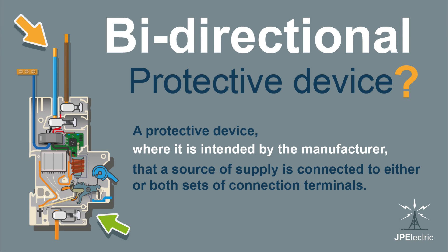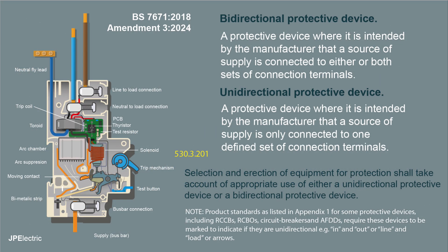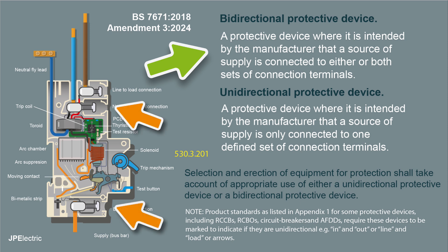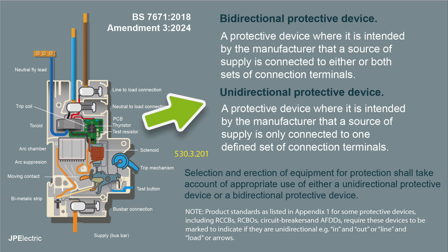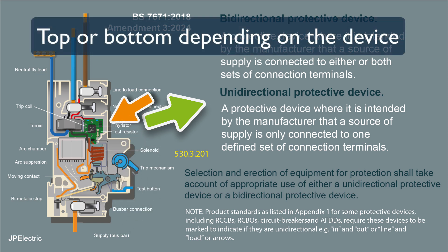Let's have a look at bi-directional protective devices and what they are. A bi-directional protective device is a device where it is intended by the manufacturer that the source of supply is connected to either or both sets of connection terminals. A unidirectional device is a protective device where it is intended by the manufacturer that the source of supply is connected to one defined set of connection terminals.